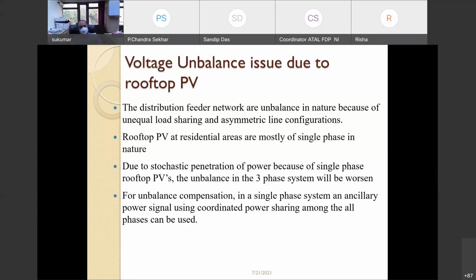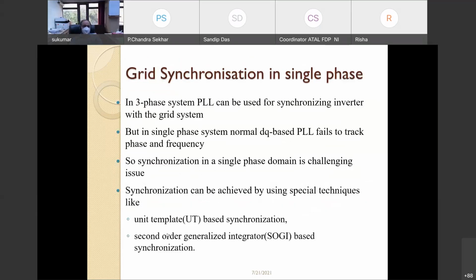However, if we properly control that, then that becomes an advantage to us, where we can properly manipulate the current so that the unbalancing can be properly addressed. As I have already mentioned, to have the synchronization, we have to go for a PLL, and generally we use DQ transformation to achieve the PLL. On the contrary, to go for a single phase PLL instead of a three-phase one, we need a different approach, and generally we go for the unit template approach or the SOGI based approach.